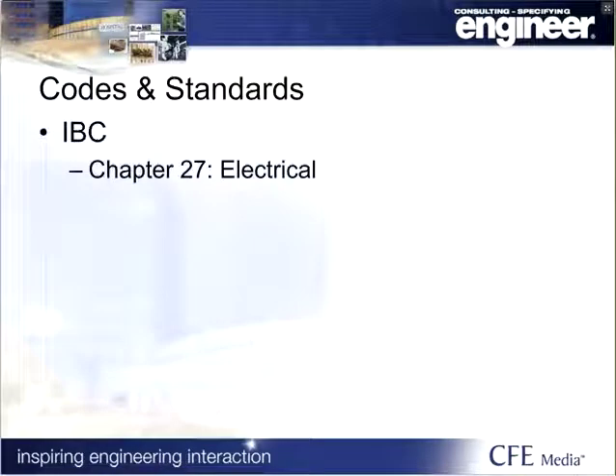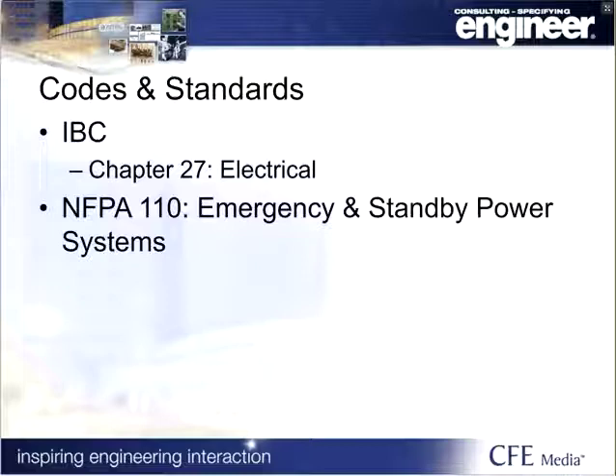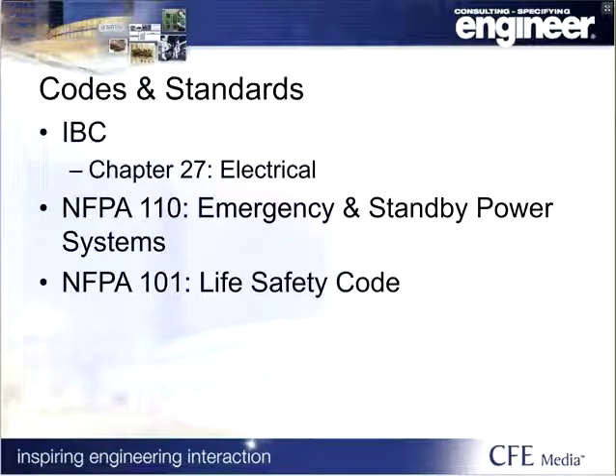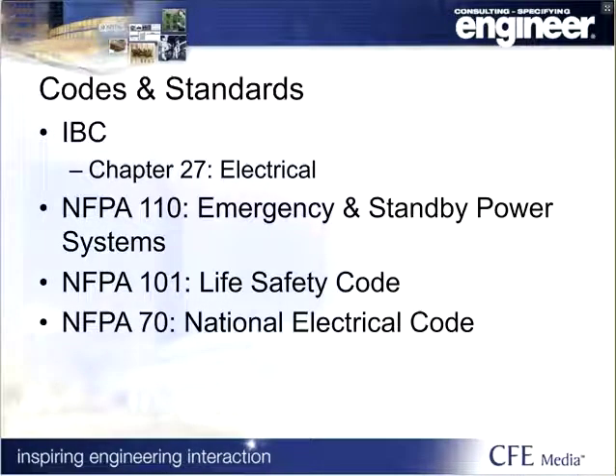One of the more prevalent codes enforced by AHJs is the IBC. Chapter 27 deals with electrical requirements, including when and how generators should be considered. There's NFPA 110, which contains criteria for generators used for emergency and standby power systems. There's NFPA 101, also enforced by many AHJs, and contains specific references to the type of backup power required in different applications. Finally, we'll look at NFPA 70.